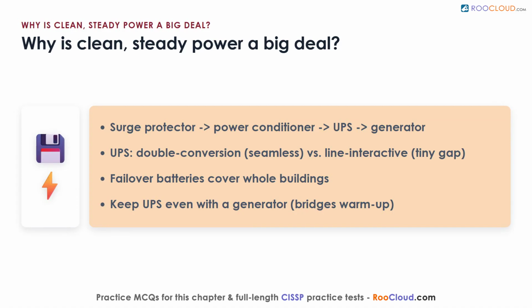An uninterruptible power supply climbs higher, using a self-charging battery to deliver clean, conditioned power and to carry the load briefly when the grid drops. A double conversion type always runs power through its battery for a seamless feed, while a line interactive type switches to battery only when the grid fails, sometimes with a tiny gap. For whole building coverage, there are large failover batteries, and at the top sit generators, which start automatically and with enough fuel run for a long time. Keep the battery even with the generator, since it bridges the minutes before the generator warms up.